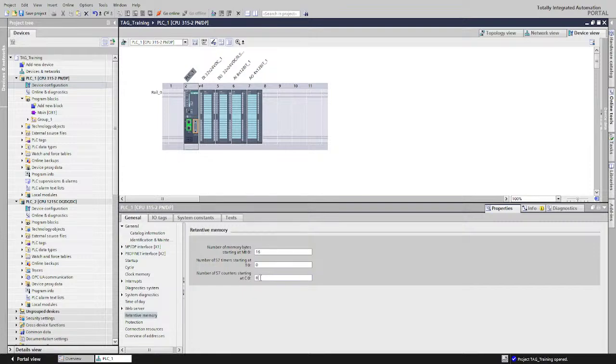One, two, two, so like this, it clears whatever is in the retentive memory. That's why most times you see people say, there's an issue, let's just restart the system, and they just power up and power up and it's not going to work out until you reset. Sometimes people think that when you press that reset, it clears the program from the PLC. No, it clears the retentive memory area of the CPU.